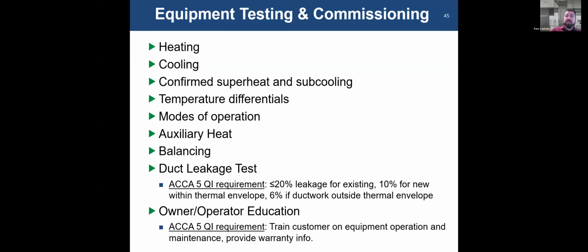It specifies requirements for duct leakage testing. Most districts that I know of don't necessarily require duct leakage testing at this point in time. However, some are starting to adhere to this. This is more so a commercial procedure where you pressurize the duct, figure out how much air you're leaking out of that ductwork, and therefore you get a leakage rate. So it gives you the guidelines. And I think this is actually in alignment with the IECC.